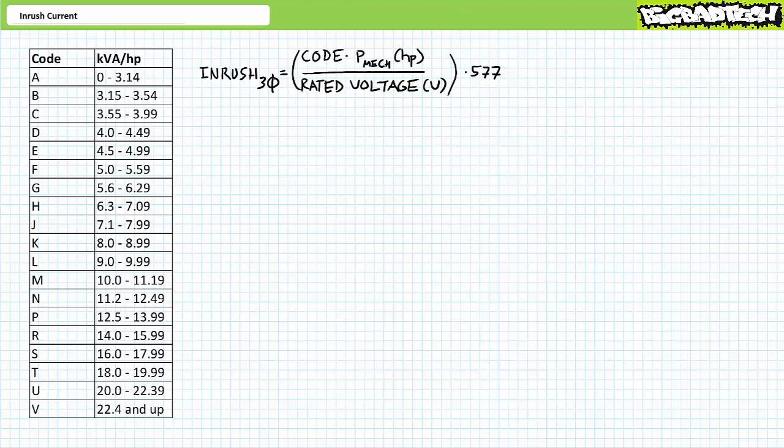For this reason, reduced voltage starting techniques like primary resistor reduced voltage starters, part winding reduced voltage starters, Y-start delta run reduced voltage starters, and soft starters, among other techniques, are employed to reduce inrush current and mitigate its negative effects. Lacking these techniques, a technician must at times calculate the anticipated inrush using the information available on the motor nameplate, so that wire size and instantaneous demand in the electrical distribution system can be predicted in advance.